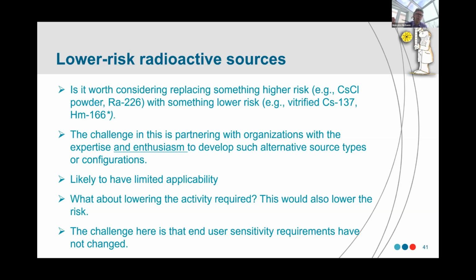There's also an idea of, can we lower the activity? Can we, going back to that early picture, can we do a measurement in a self-shielded strontium-90 source, which is very easy and very low risk? Can we use that to issue a calibration? But we have to keep remembering that it's our end user sensitivity that we have to focus on, and there's a disjoint then between measurements with a low activity source at the calibration lab compared to what's being done in the end user, and we have to do a lot to bridge that gap. So again, collateral comes in of what costs are being added to by making these changes.